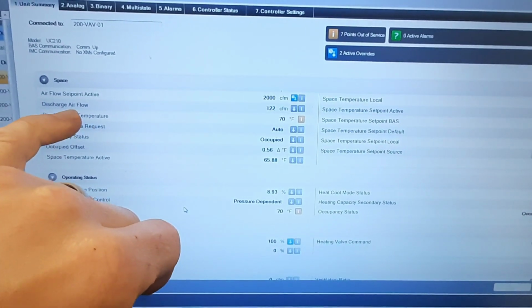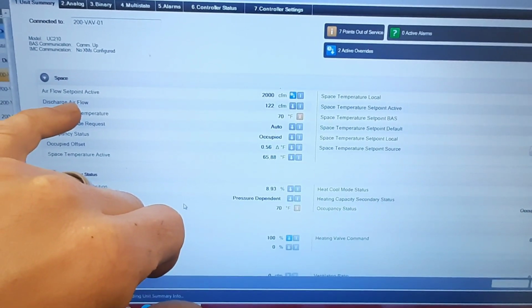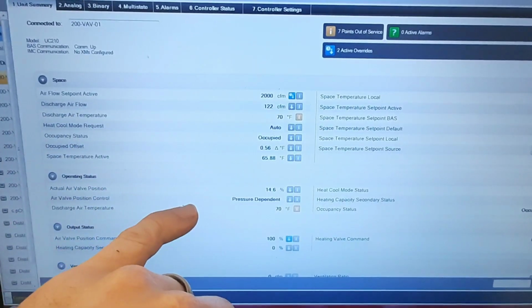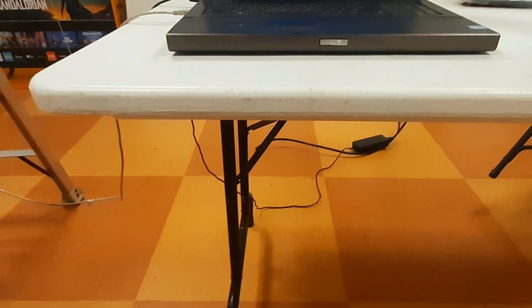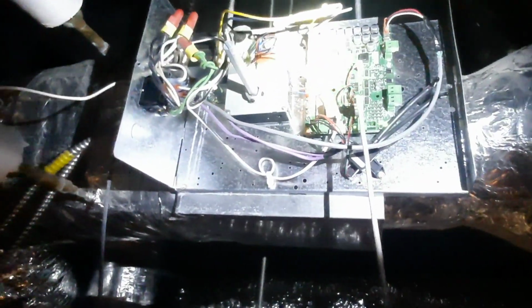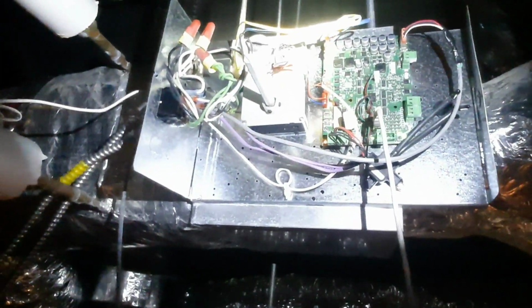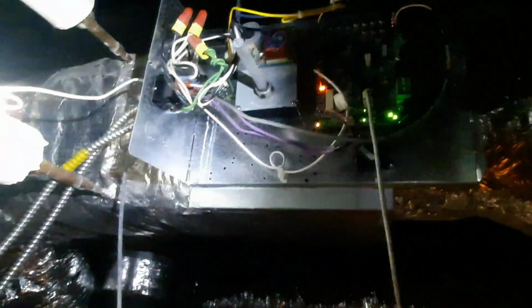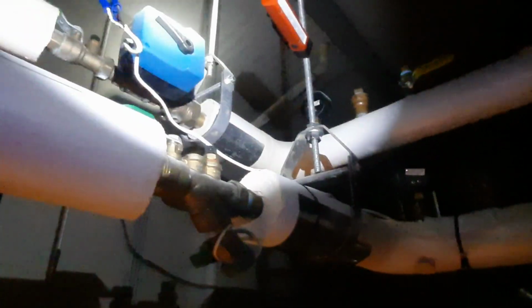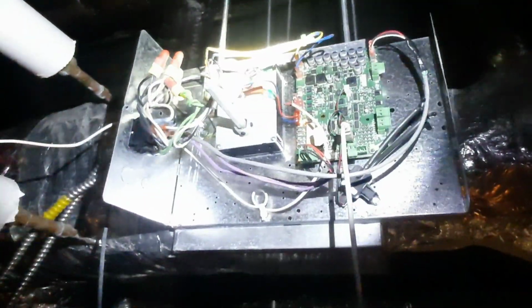So I overrode my airflow set point active, which was at 0. Put it at 2000 and it seems like my damper's actuating now. So I'm gonna have to figure that out. Let's make sure my damper's moving. There she goes. Starting to open up. So that's a start. We'll let it get to 100%. I've got to actuate that hot water valve too, just to make sure it works.